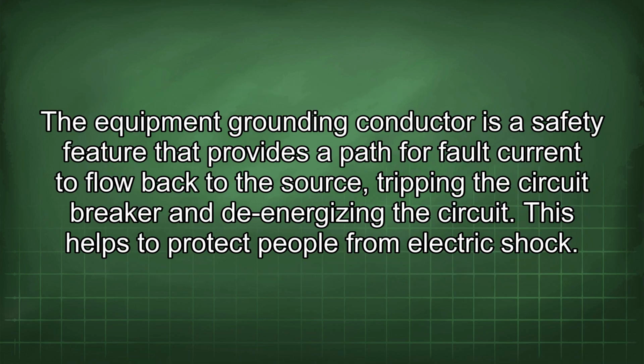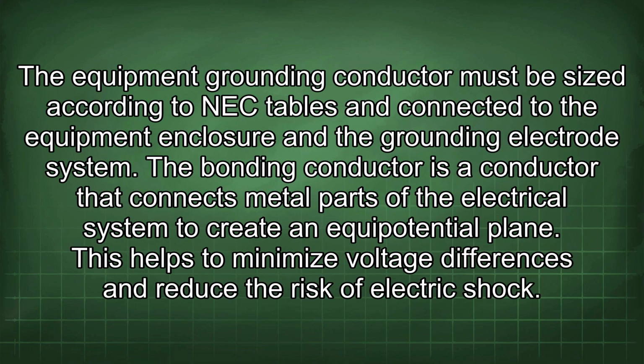The equipment grounding conductor is a safety feature that provides a path for fault current to flow back to the source, tripping the circuit breaker and de-energizing the circuit. This helps to protect people from electric shock. The equipment grounding conductor must be sized according to NEC tables and connected to the equipment enclosure and the grounding electrode system.